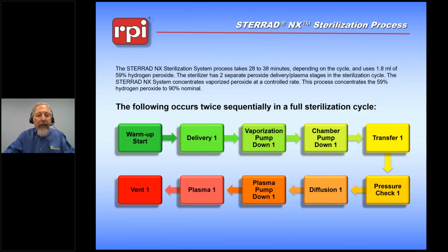Okay, so this is what the peroxide process looks like. Basically what we do is we put our material into the chamber. We allow all of our surfaces to acquire the correct temperature so that we can control where the hydrogen peroxide is and where it winds up going. And then once that system is warmed up, we deliver the peroxide from the chamber to the vaporizer, pump down the vaporizer, we then deliver it to the chamber.